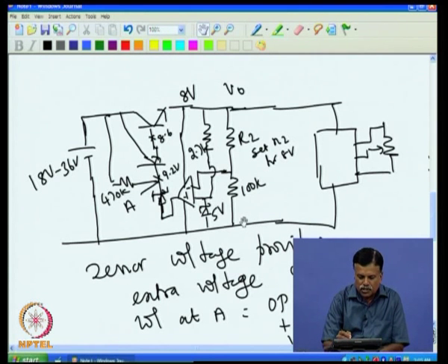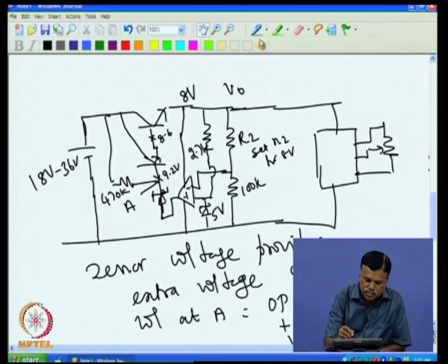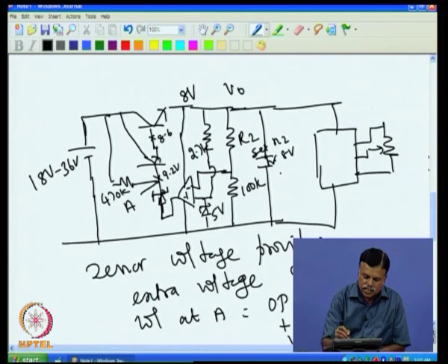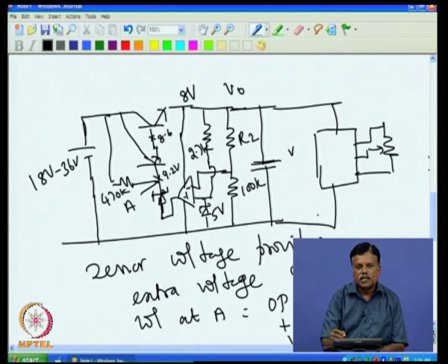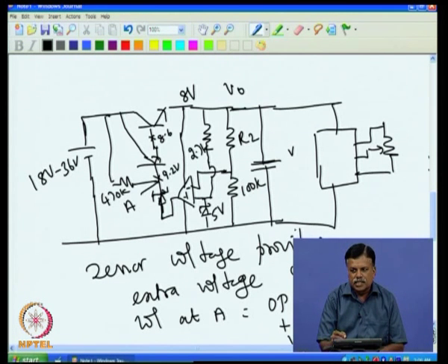And then we know that to avoid oscillation, we had connected the capacitor here. A small capacitor can be connected across this, so that no oscillation comes in. Normally we put a capacitor here, but here we cannot put an electrolytic capacitor, because this is a 4-20 milliampere system, and if the electrolytic capacitor leaks after some time, then the current drawn by this will upset the other current in the unit, and that will create a problem.